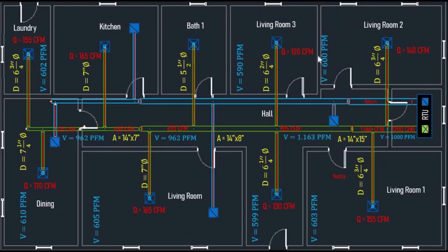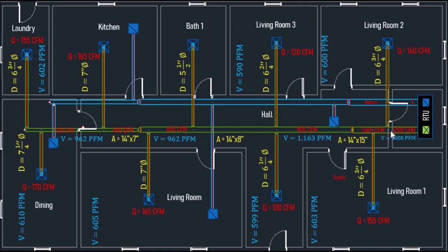As you can see, I have drawn a duct layout showing 1200 CFM with a velocity of 1000 FPM flowing through our main supply duct, which has a cross-sectional area of 14 by 15 inches, minus 140 CFM with a velocity of 600 FPM flowing through a flex duct with a diameter of 6 and 3/4 inches. That leaves 1060 CFM, then minus 155 CFM with a velocity of 603 FPM flowing through a flex duct with a diameter of 6 and 3/4 inches.